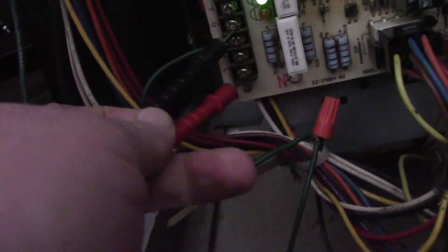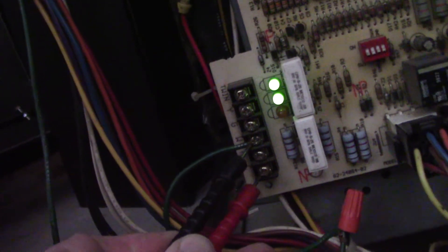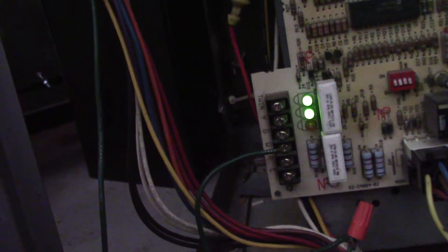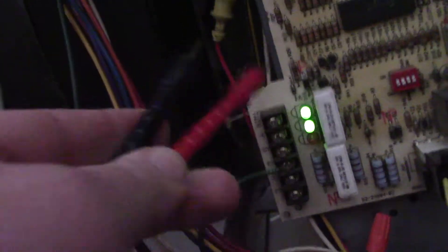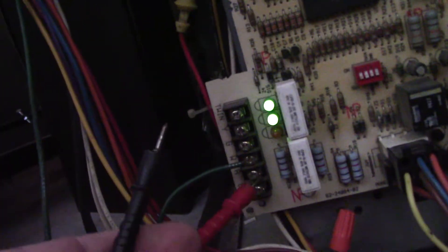But there are four instances I've come across where I can go W to common, get 24 volts, and the furnace still doesn't run because somebody at some point crossed the thermostat wires. The W becomes the hot leg while the red wire became kind of a common leg. So if you go W to C and you have 24 volts but the board's not throwing a diagnostic light or running, somebody's probably switched the polarity on the wires. Therefore you're going to read it, but the thermostat still has no output. Remember, R is the output to the thermostat, W comes back as input.